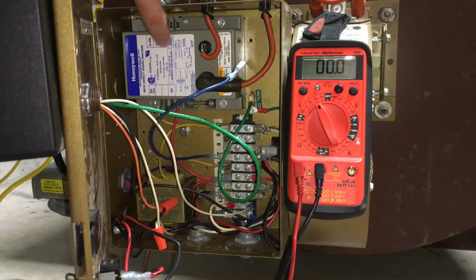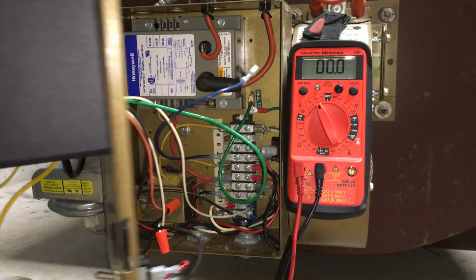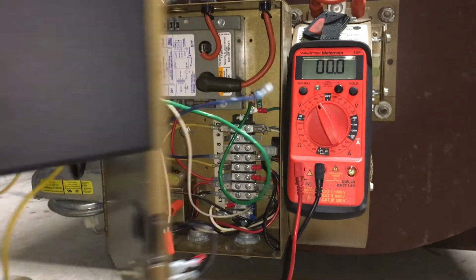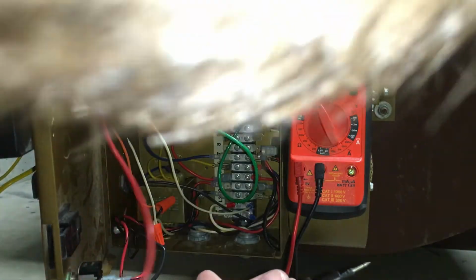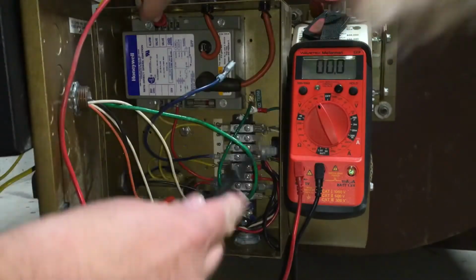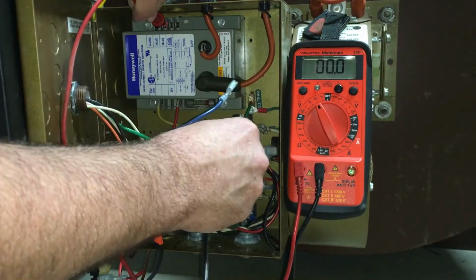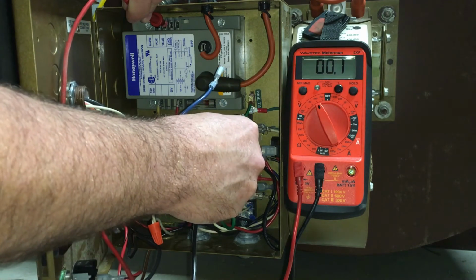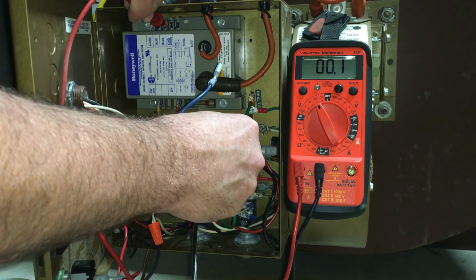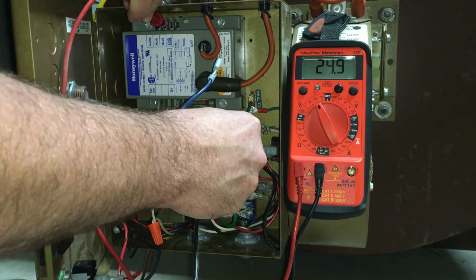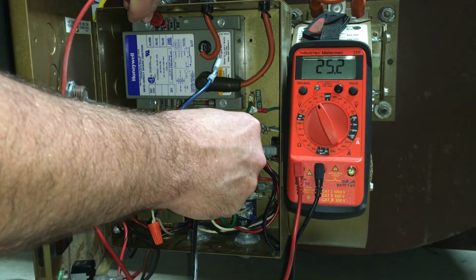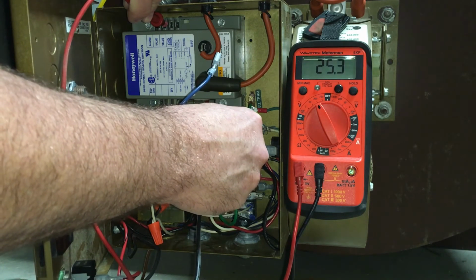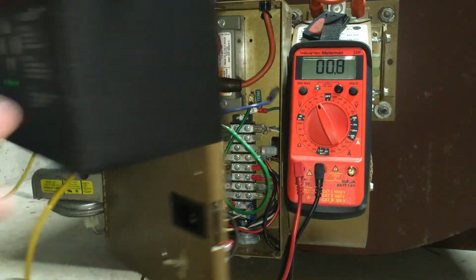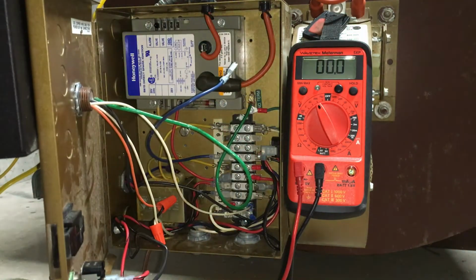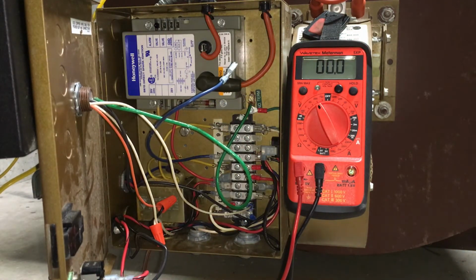So you can see now we pulled the wire, the blue wire, off of the ignition control. So we'll start the system back up. Across the 24 volt terminal in the electronic ignition and the 10. As the ignition system kicked in, you can see we now properly have voltage to it. So replacing the fuse took care of that issue.